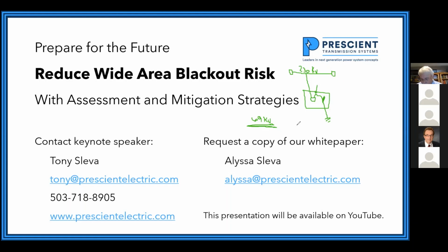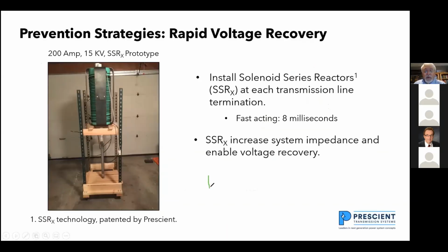You were explaining the, I don't remember, the thing that you connected at the end of the lines to increase the voltage. Oh, the solenoid series reactor. Right. If I have a transmission line today, what I do is I put a circuit breaker in here, and then I have the transmission line run from here to someplace else. So I'm showing this is a transmission line with circuit breakers on both ends of the transmission line. And then if I put a solenoid series reactor in right here, and I put a solenoid series reactor in here, under normal load conditions, the impedance of this reactor would be, say, 1 ohm. So this is a 1 ohm reactor, and this is a 1 ohm reactor.